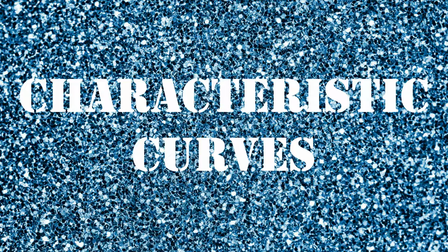Welcome to my channel. Today I'm gonna talk about the obturator determines the flow characteristic of the valve, that is, the relationship between the shutter stroke and the flow rate of the fluid. The characteristic of an incompressible fluid flowing under conditions of constant differential pressure through the valve is called the inherent flow characteristic and is usually represented by considering the valve plug travel as an abscissa and the percentage of maximum flow under a constant differential pressure as ordinate.